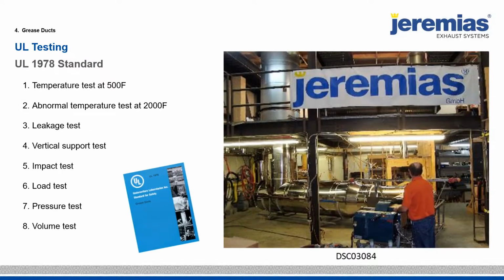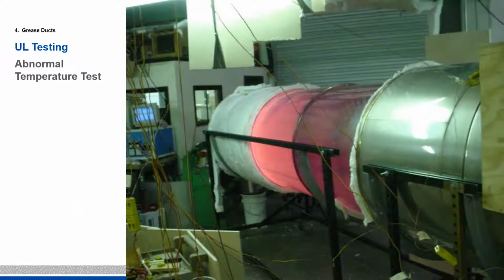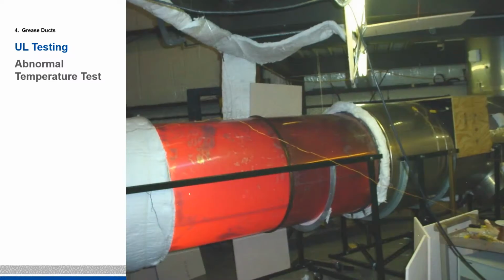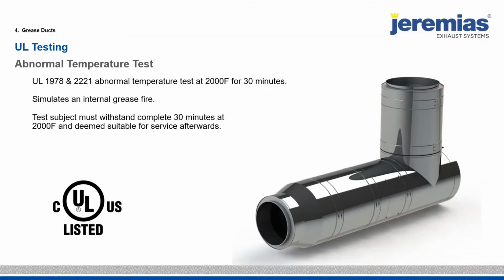And we're going to be looking at some test procedures for this 2,000-degree abnormal test. This test is to simulate a kitchen exhaust fire, which happens all the time. Actually, NFPA 96 talks about $200 million of direct damage due to kitchen fires every year. So just to start with, I want to show everyone what a 2,000-degree stainless steel duct looks like. So this duct we're seeing pictures of is at 2,000 degrees inside our lab. So let's talk about the test procedure. This is a 2,000-degree test for 30 minutes.